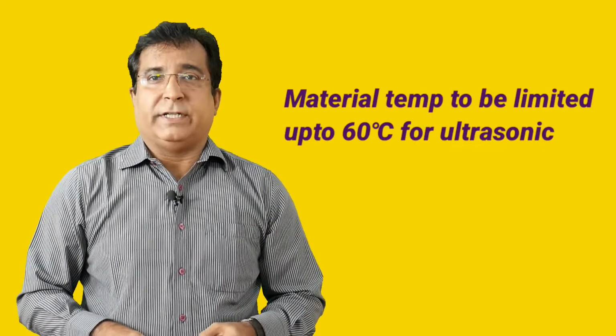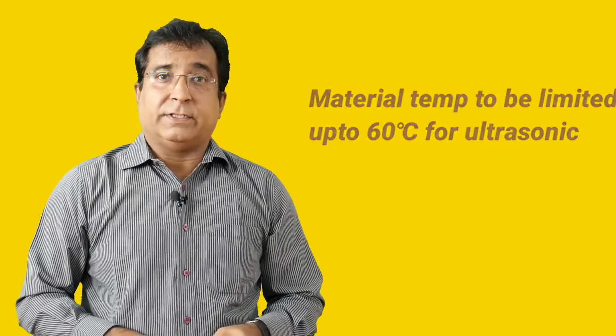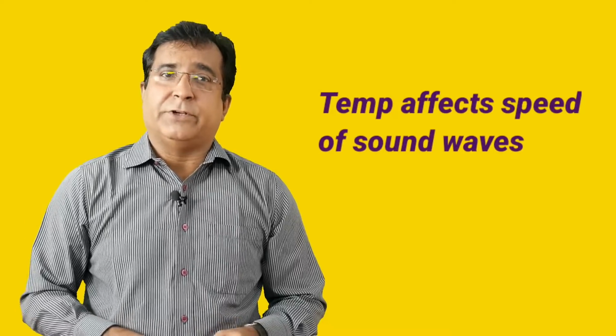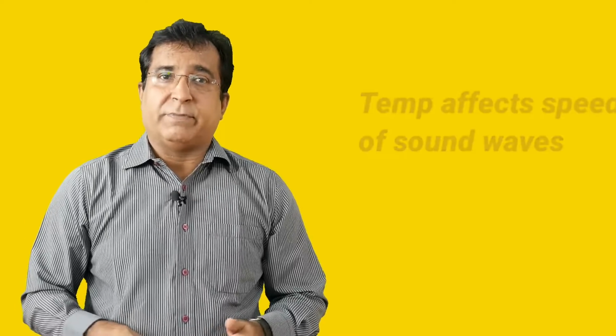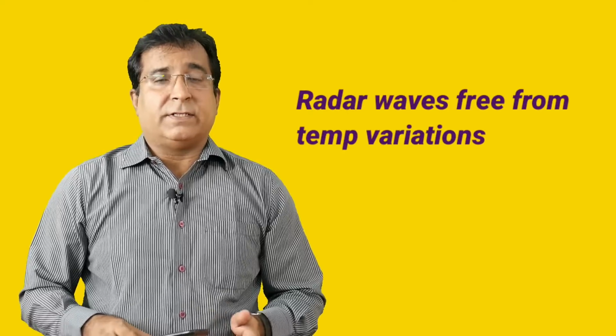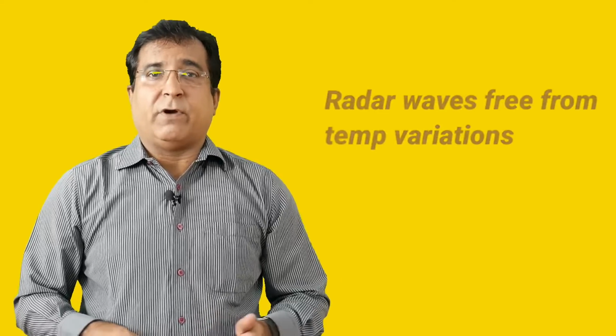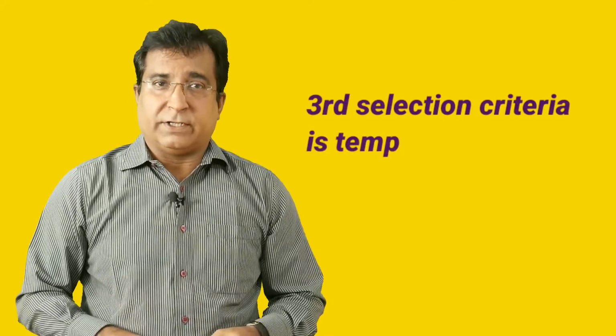Now, the next criterion is the operating temperature of the material. It must not exceed 60 degrees Celsius for ultrasonic level, and this is a condition. It must also be constant to achieve a high level of accuracy. Temperature variation may cause inconsistency in measurement and disturb calibration, due to the change in sound wave speed with temperature variation. While radar sensors are less affected by temperature and provide repeatability and accuracy in measurement. So this is the third criterion of selection.